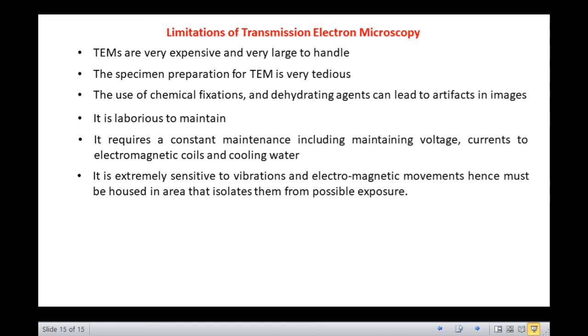The TEM is very laborious to maintain. It requires constant maintenance including maintaining voltage, currents to electromagnetic coils, and cooling water. It is extremely sensitive to vibrations and electromagnetic movements, hence must be housed in an area that isolates them from possible exposure. It produces black and white images unless a fluorescent screen is used at the end of the visualization.